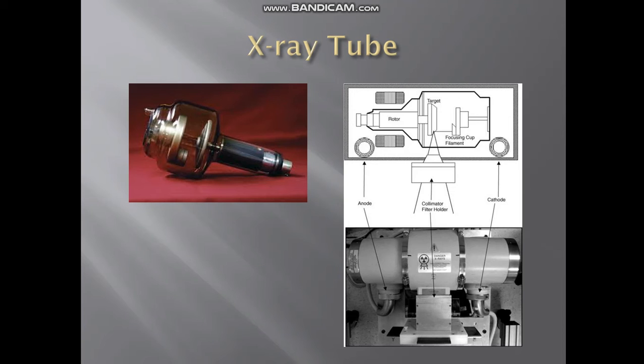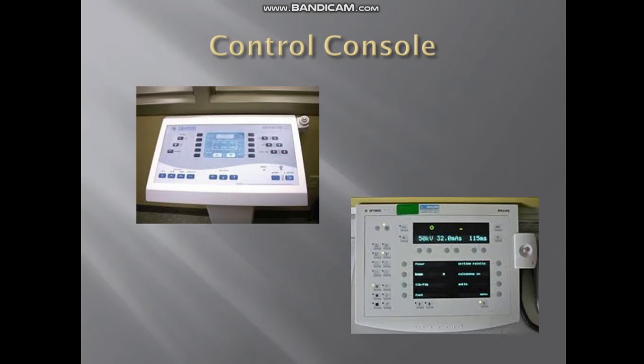For the second component, we have the operating console, most commonly known as the control console. This component allows the radiologic technologists to provide input on the X-ray tube current and voltage. Current determines the quantity, while the voltage determines the quality of the X-ray beam.